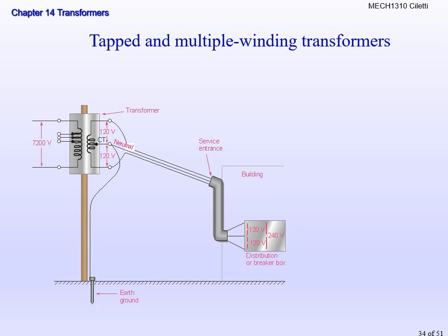You might have 7.2 kV of power coming across here, and we do different taps to pull off all the different 120s, then service that into your building. You can use your transformer to take those two 120s and tap it up to 240, or use split phase. Notice that every pole has that wire going down — that's earth ground, with about a 6-foot rod sticking into the ground for protection and grounding. This is really what's inside those big cylinders you see when you're driving down — just a big transformer with different taps we can use to get different voltages.